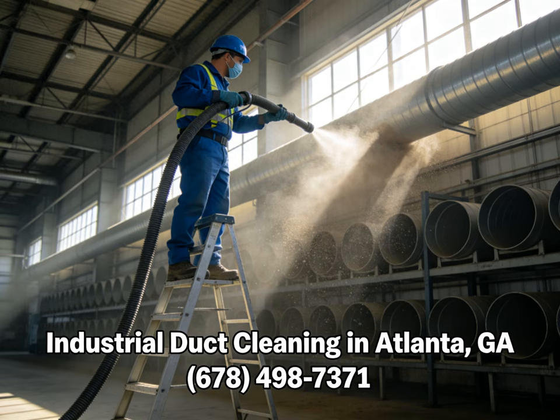So the sources state they use negative air machines. Rather than just sticking a giant vacuum hose in one end, they seal the entire duct system and use this machine to pull the internal air pressure lower than the air pressure outside the ducts. Yes. Creating a negative pressure environment ensures that as contaminants are knocked loose, absolutely none of it escapes into the building's ambient air. Oh, I see. The atmospheric pressure differential just forces everything toward the collection machine.